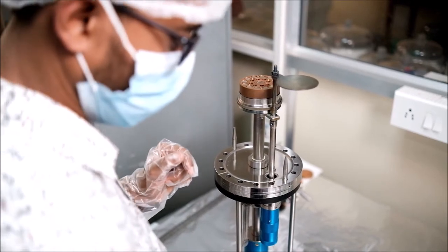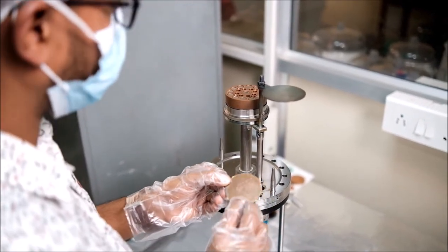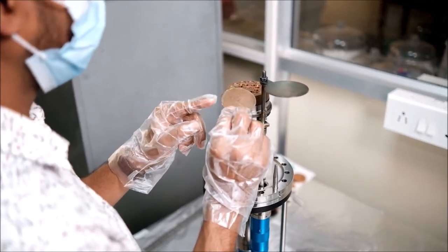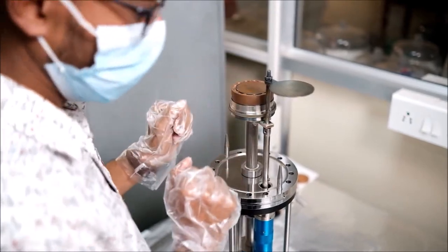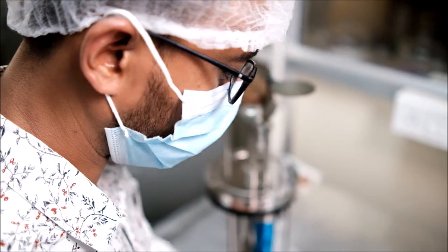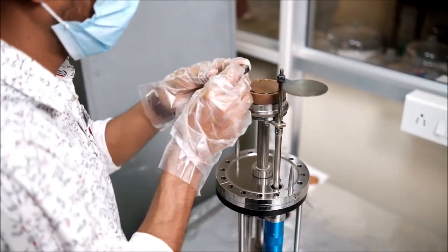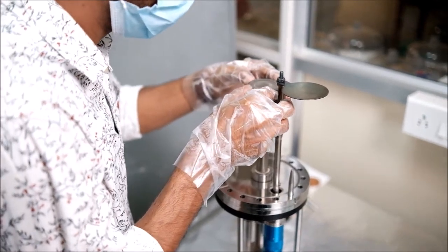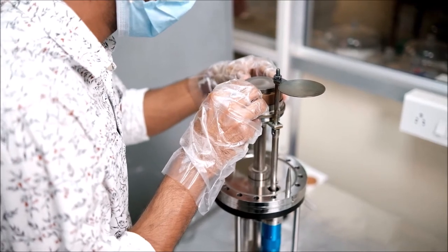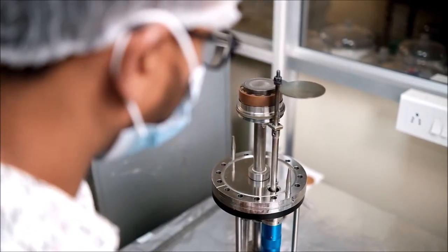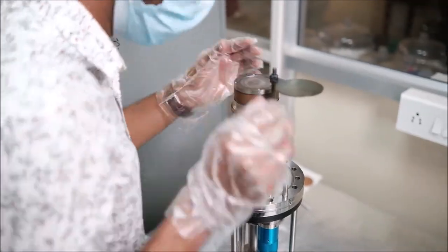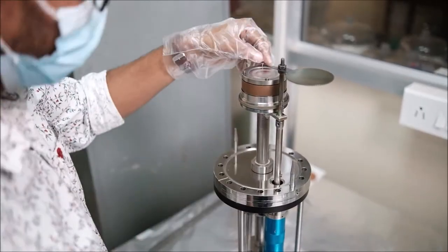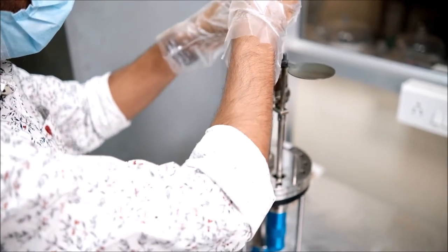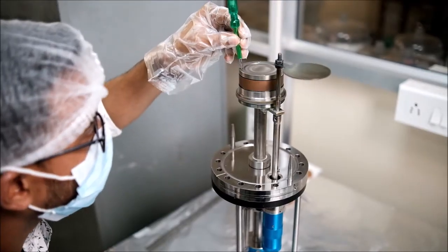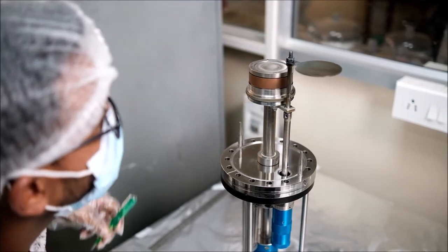Now we will attach the target onto the gun. So first we will use a back plate, and on top of it we will attach the target so that the target material does not contaminate. So I have attached it, and I will take a tungsten target for demonstration purposes. So this will hold it. On top of this, there is a groove. With the help of the groove, we'll attach it. And then with the help of this gasket and this screw, we'll attach it. While tightening the screw, we should be careful not to tighten it very tightly. And we have to see whether it is uniformly tightened all over the disc area or not.